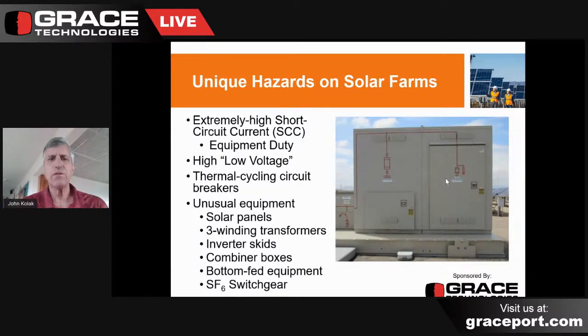Now, some of the unique hazards that you'll encounter on solar farms. Well, one thing that's not unique is that we have extremely high short circuit current on solar and wind farms. Remember, if you have a system that produces, say, 300 to 500 megawatts of generating capacity, if you have a transmission system that can receive 500 megawatts of generation, if there's a fault on the farm itself, of course, it'll give you that back and some change as well. So we always need to realize when you're working with systems that can receive that kind of generation, there's a tremendous capacity there for short circuit current as well. And that has to do with something called equipment duty. Equipment duty is a concept that compares the actual interrupting rating of a protective device to the actual short circuit current to which it would be subjected.